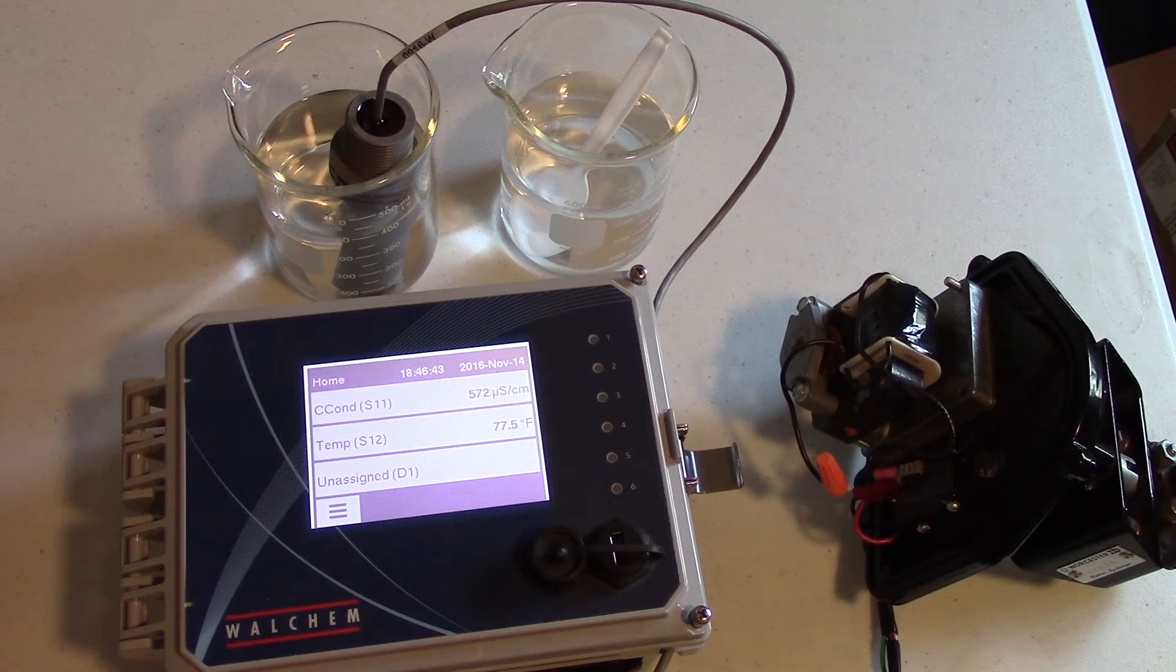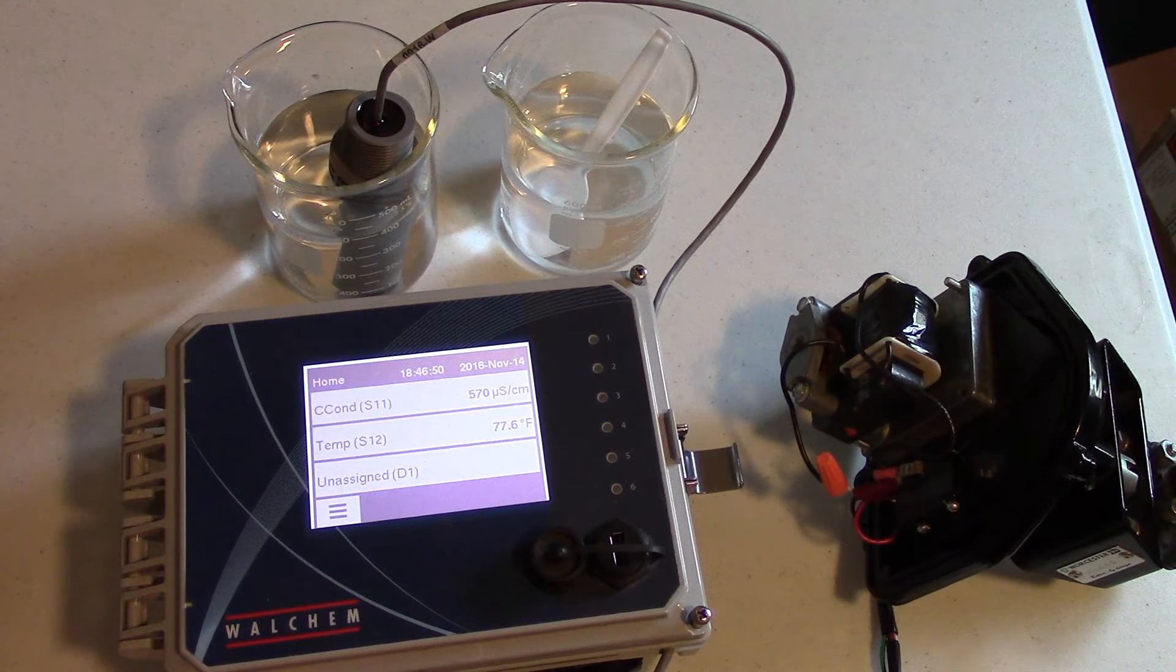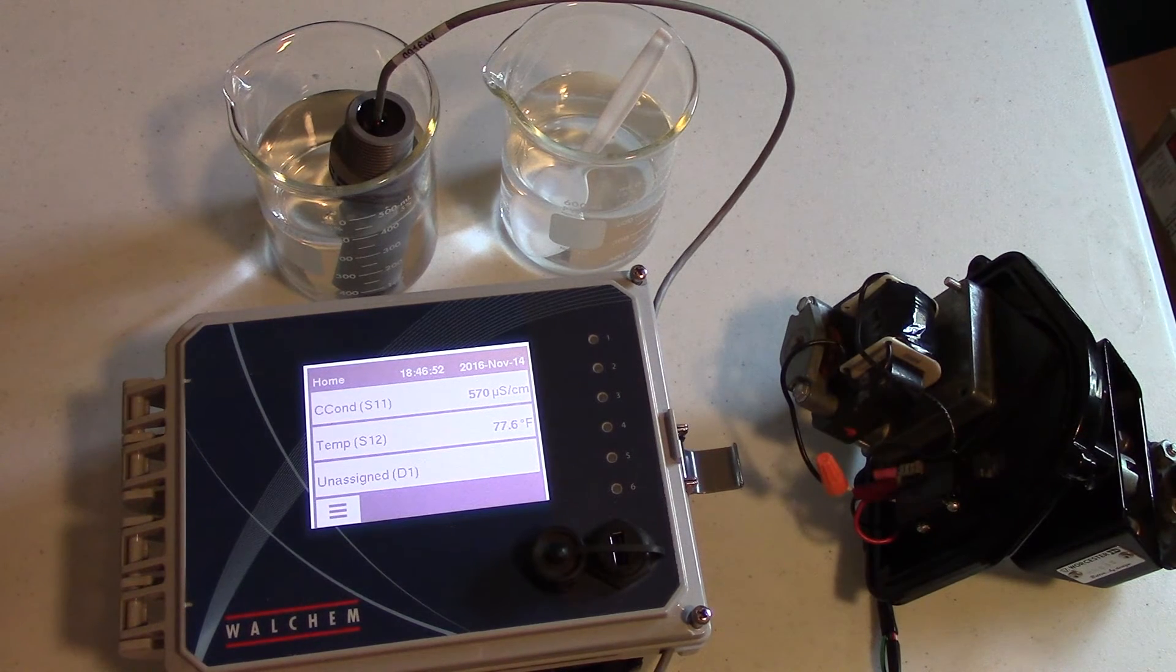And then the valve closes. And so you notice there's a longer time between open and close and close and open than the solenoid valve. So you need to keep that in mind when you're programming your set point and your dead band.